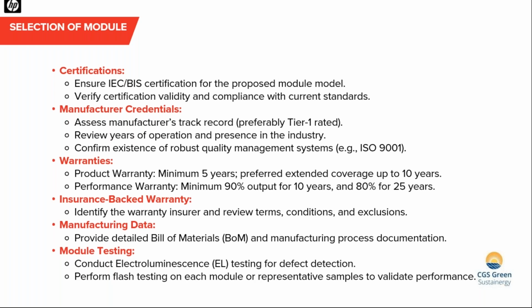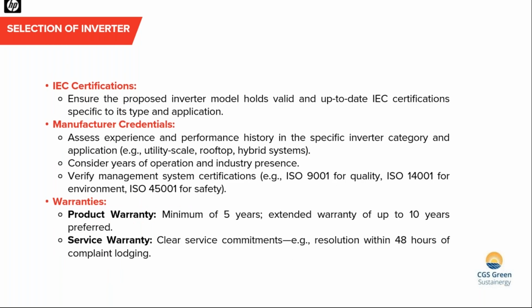Module testing usually involves the electroluminescence test, which helps us detect micro cracks in the modules. We also do thermography, which helps identify hotspots in the module - if there's small damage, a hotspot gets created in that area and the module overheats there. Inside, there's a ribbon connecting each cell, so if that's damaged, generation won't happen for that particular string. That's one major reason we do this testing and thermal imaging for modules.